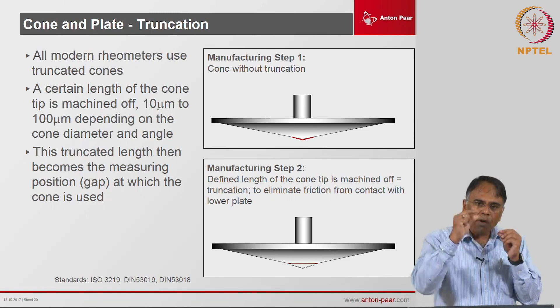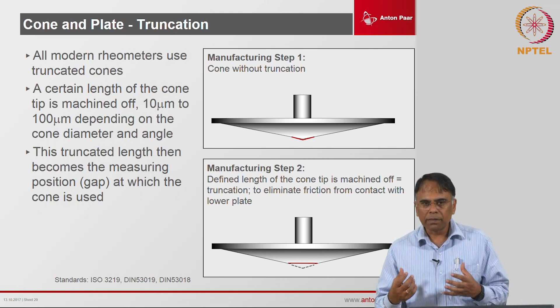So, if you are measuring at 50 degrees, you do the 0 gap and you set the gap at that 50 degrees and measure at 50 degrees, that is it. You cannot then change from 50 degrees to 40 degrees without doing a 0 gap again. So, it is very important in a cone and plate to measure at isothermal conditions only. And you cannot measure with larger particles, because these particles can come at the tip, can get trapped at this small gap, and then you are actually measuring only those small amount of particles which are trapped over there, and you get problems. So, it is, I would say, not the best geometry for measuring slurries or dispersions with large particles. For homogeneous fluids, it is best. No problem at all.